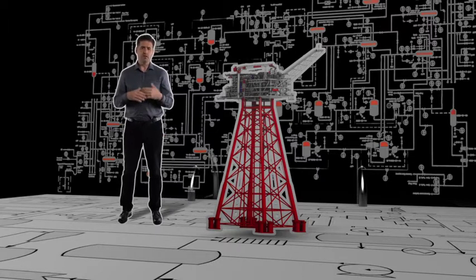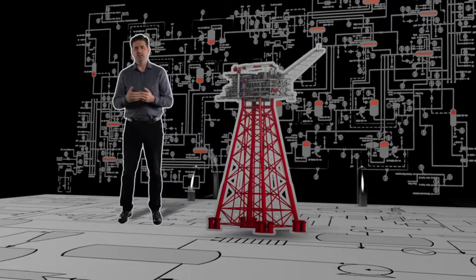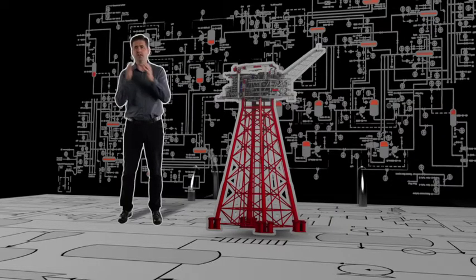In that way, we don't have to rely on secondary systems such as shutdown systems and protective systems to keep them safe. The considerations of engineered systems is more about detailing the systems that are there to protect, such as relief and blowdown systems and shutdown systems. So the basic architecture of codes covers the breadth of inherently safer design thinking and considerations of engineered systems.